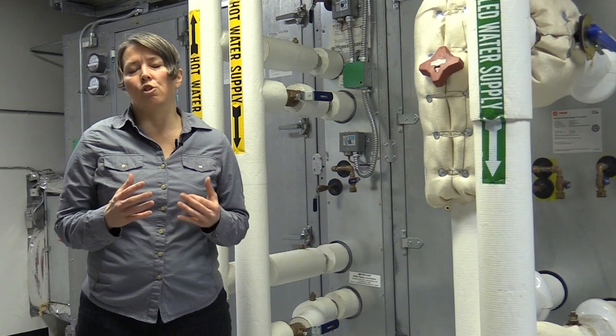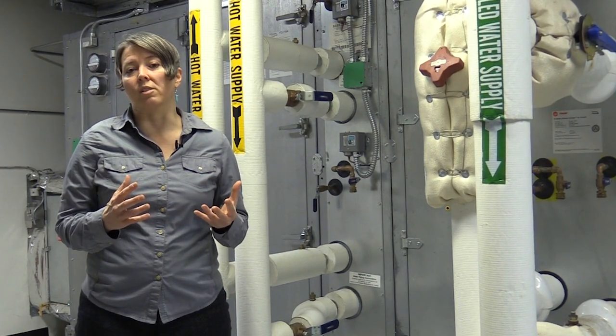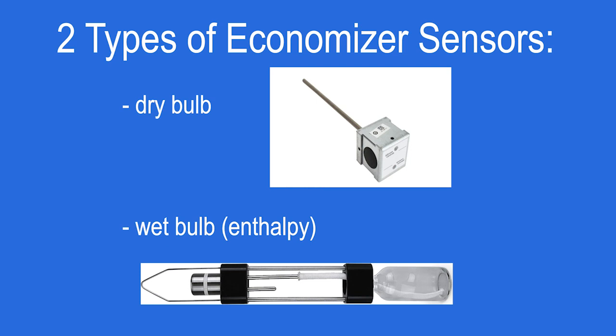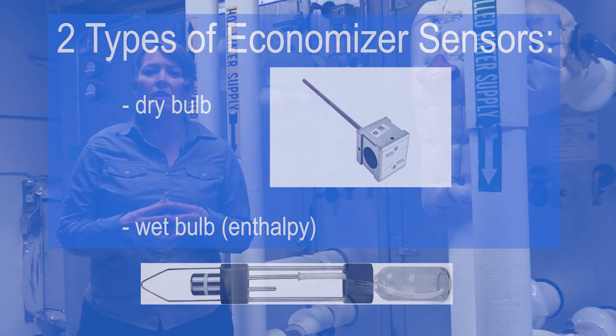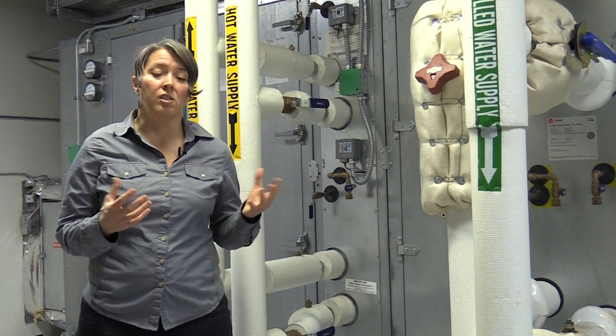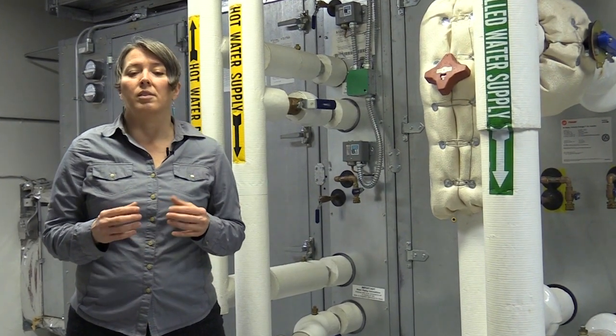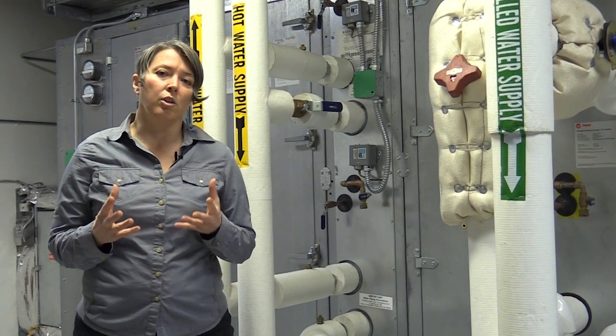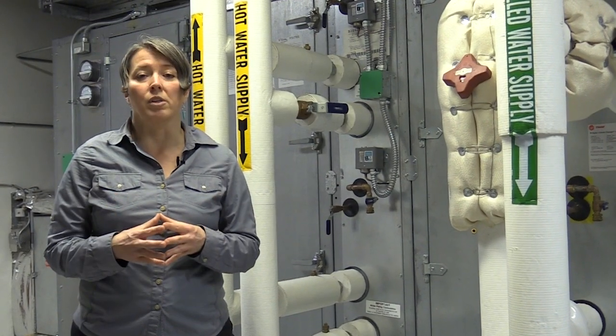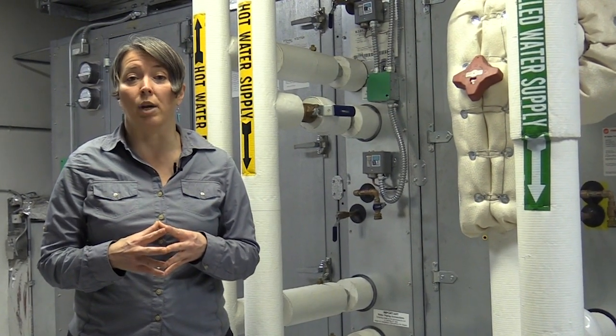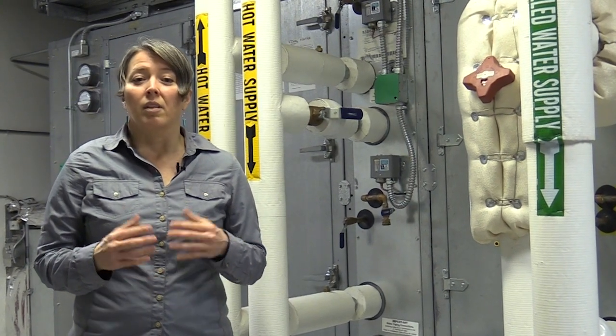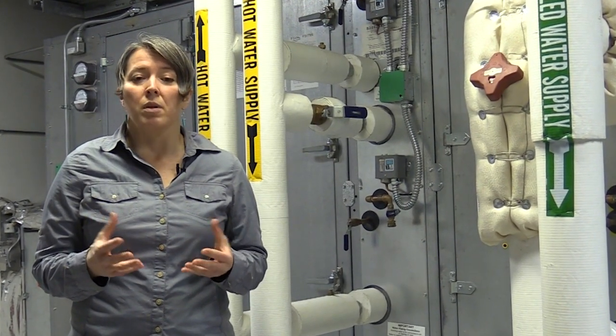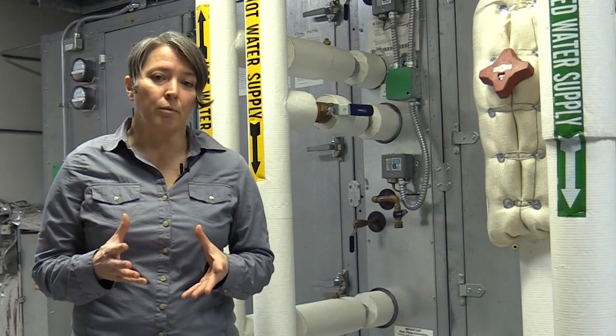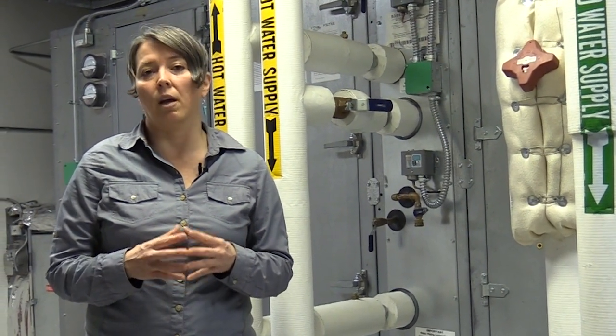And we have basically two different economizer sequences. One uses a dry bulb sensor, and the other uses a wet bulb temperature sensor or enthalpy method. In this video, we'll look at this system, which uses a dry bulb sensor. And these are a little simpler, a little more reliable. These should be checked for proper calibration at least once a year. The enthalpy type of control is a little more prone to failure and should be rechecked at least twice a year.